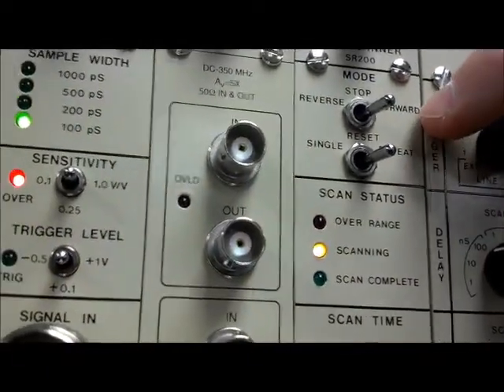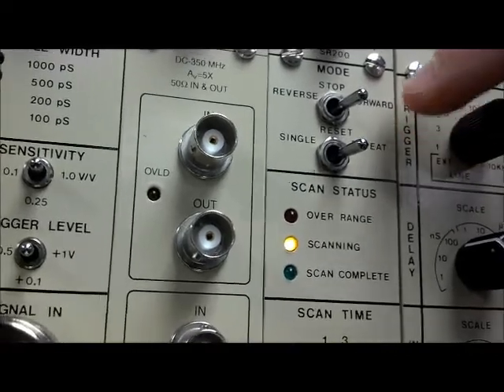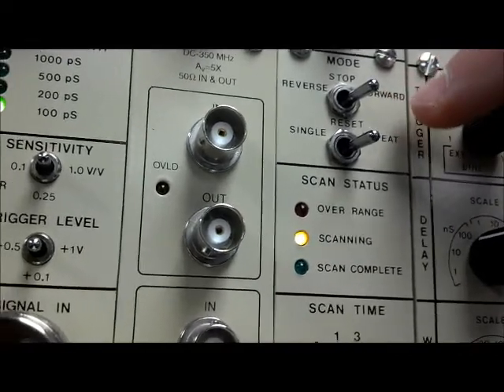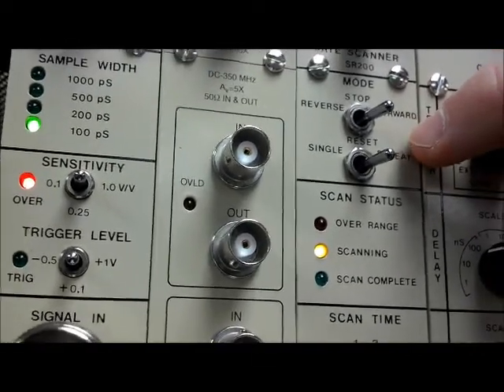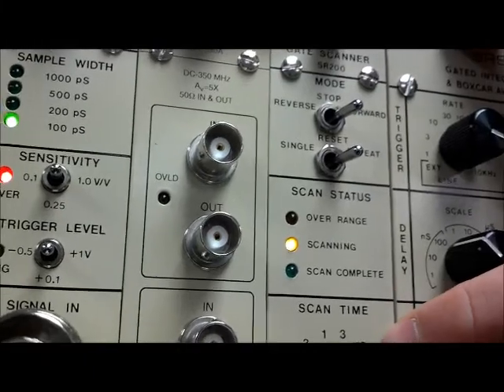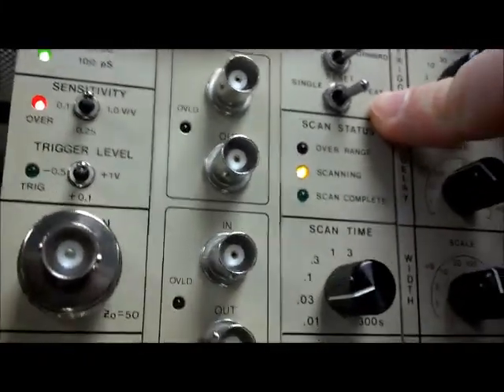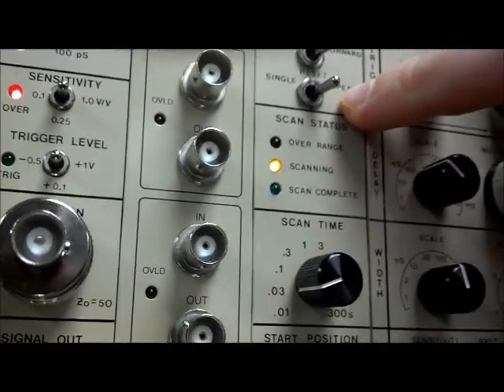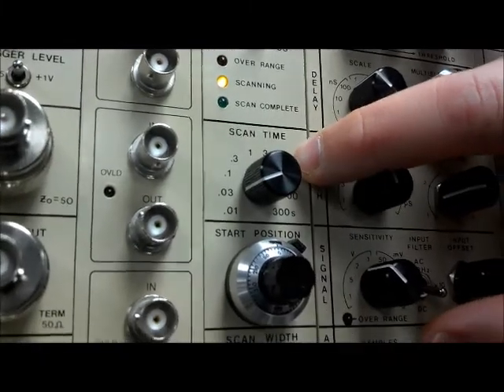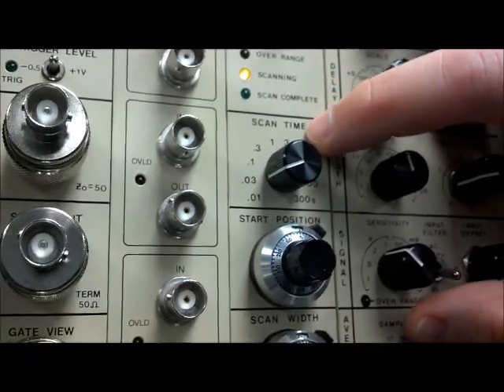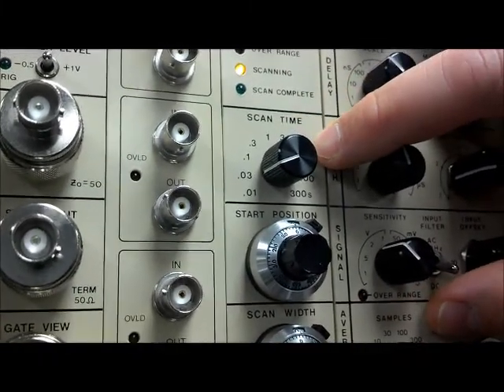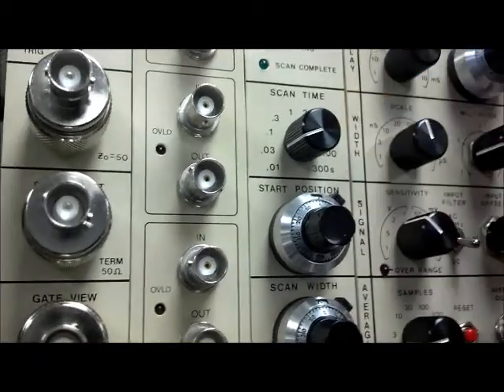We have single or repeat. The single mode would only scan through a complete time as set by the scan time one time, whereas the repeat mode continually repeats the scan time. The scan time knob allows the user to set the amount of time that the waveform is scanned from. This can be adjusted from 10 milliseconds up to 5 minutes, or 300 seconds.